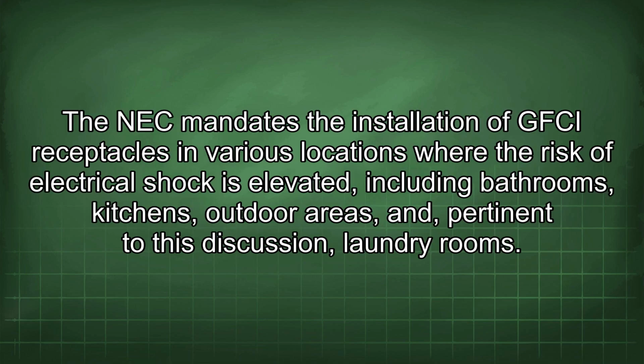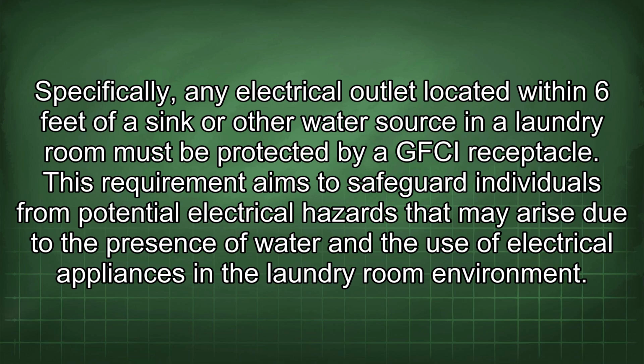The NEC mandates the installation of GFCI receptacles in various locations where the risk of electrical shock is elevated, including bathrooms, kitchens, outdoor areas, and, pertinent to this discussion, laundry rooms. Specifically, any electrical outlet located within 6 feet of a sink or other water source in a laundry room must be protected by a GFCI receptacle. This requirement aims to safeguard individuals from potential electrical hazards that may arise due to the presence of water and the use of electrical appliances in the laundry room environment.